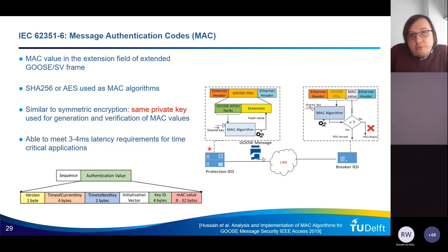So how it works: if we have an intelligent electronic device that is used for protection, then we have an intelligent electronic device that controls the circuit breaker to open, and we have a communication network in between, just in our lab setup. The GOOSE message will be sent to open the circuit breaker. Now we need to check that the integrity of this message was not changed. So the packet was not changed by an attacker who would instruct the breaker IED to open when it's not needed.